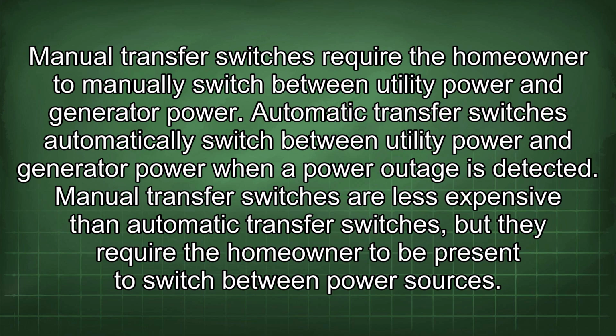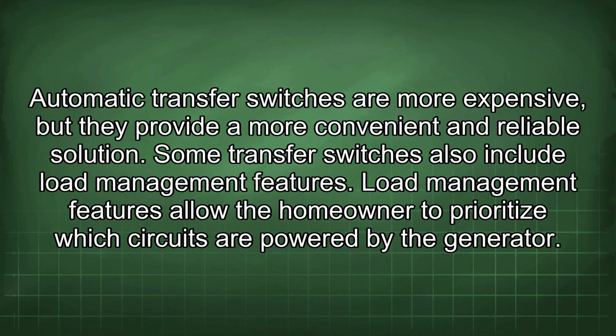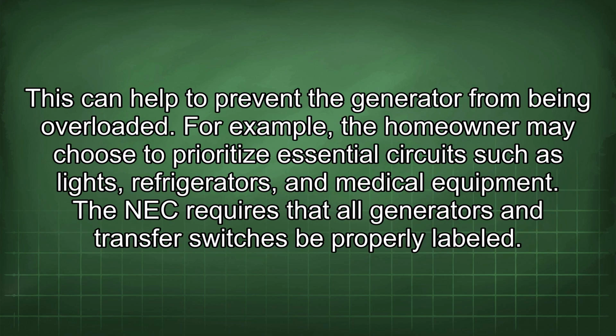Manual transfer switches are less expensive than automatic transfer switches, but they require the homeowner to be present to switch between power sources. Automatic transfer switches are more expensive, but they provide a more convenient and reliable solution. Some transfer switches also include load management features. Load management features allow the homeowner to prioritize which circuits are powered by the generator. This can help to prevent a generator from being overloaded. For example, the homeowner may choose to prioritize essential circuits such as lights, refrigerators, and medical equipment.